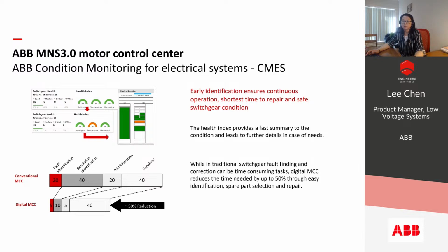The second example, shown on the bottom, outlines the difference in total repair time in minutes in case of a fault between a conventional switchgear and a switchgear with a CMES system. From fault identification, resolution identification, through preparation of paperwork and identifying spare parts, until the affected assembly is finally restored to operation, it is expected to save up to 50% of the full management process with the application of the CMES, hence increasing plant availability significantly.